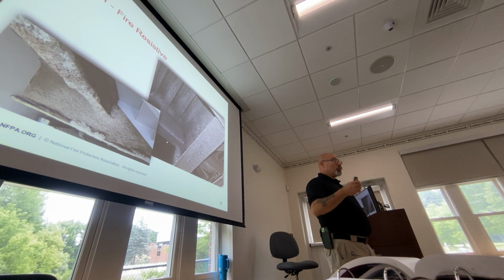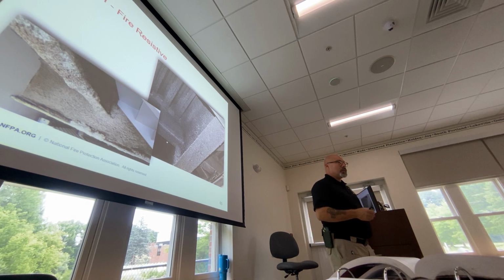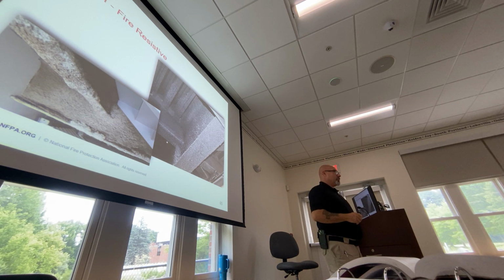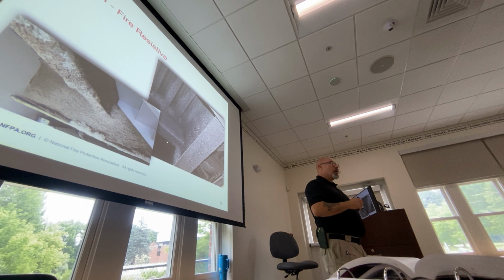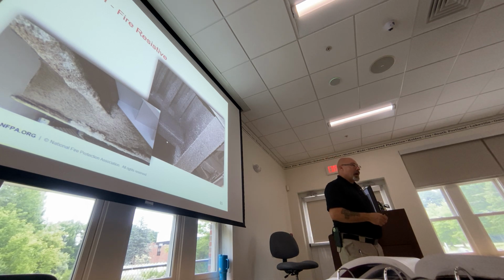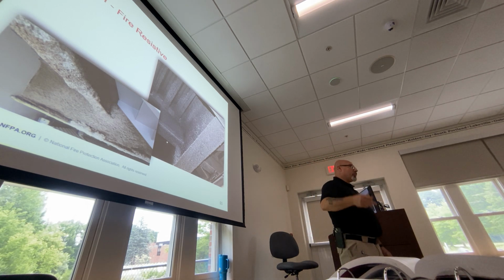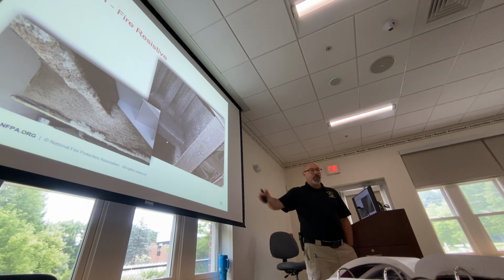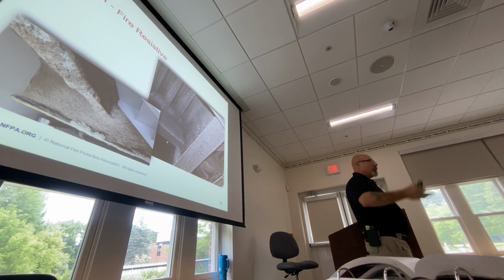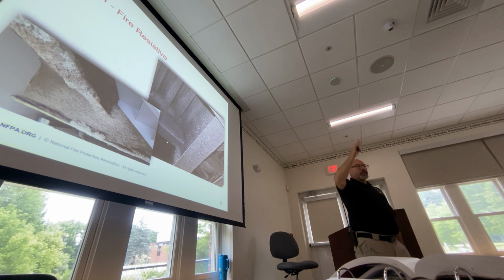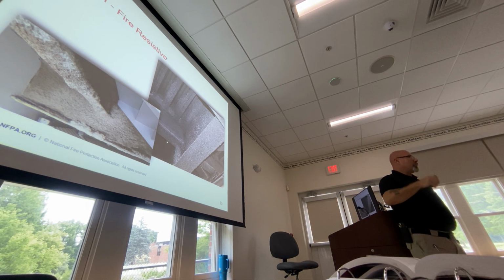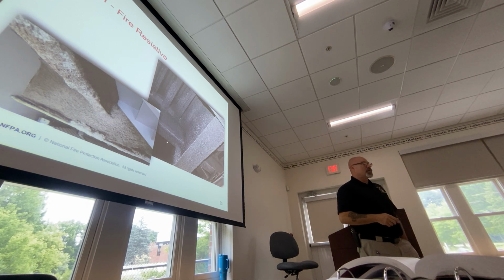So it's important to take really good notes, because how do you do your inspection and then send something in an email to somebody of what you found and where you found it, and have them go back and find it to fix it? That is very, very difficult. So you have to be extremely specific. I don't care if you have to measure 20 feet out from the exterior wall as you're going down the corridor, by door number 1, 2, 3, above the water line piping. There's an area there. Take a picture of it, circle it, attach that to your deficiency list.